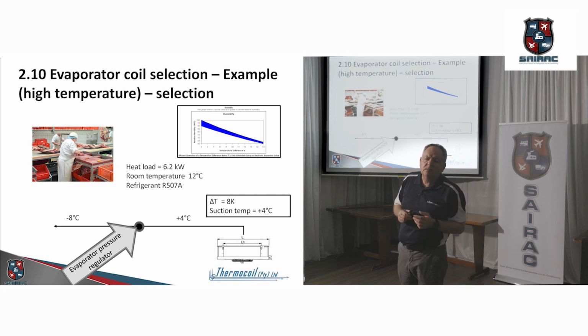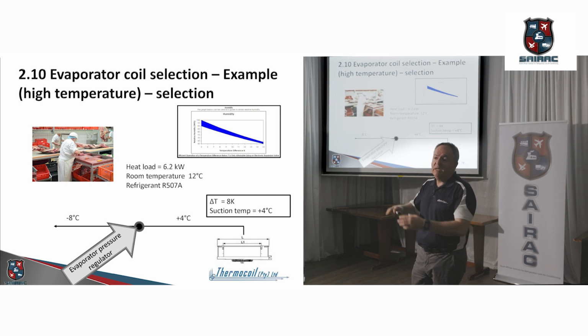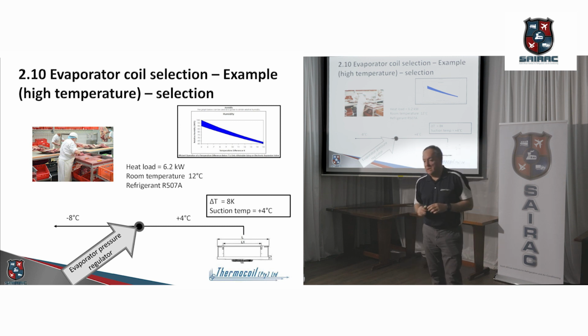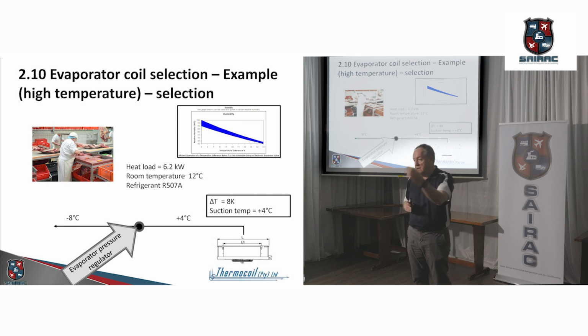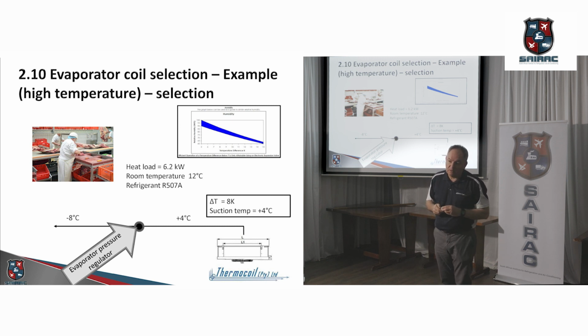So if I take it to 5, will it make a difference? It will. Yeah. So if you take it to 5, you're possibly going to need a higher surface area. And maybe you want 5 because at 5 your dehydration rate is going to be lower. But don't kid yourself. Even if you change it to 4, you will still dehydrate the air. And also the 7 and the 8 is to offer you a room condition with an RH of around 75 to 80. So it depends on what you want to, of course, keep your product at.